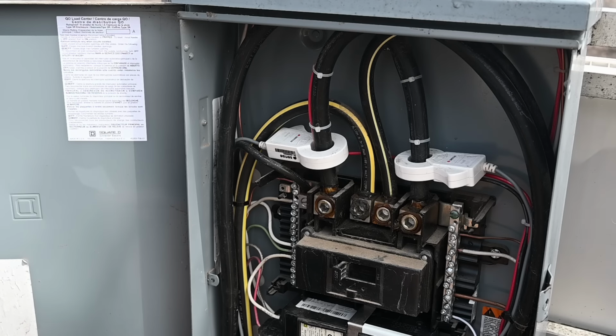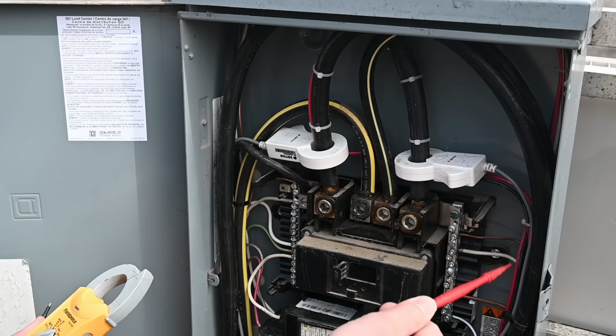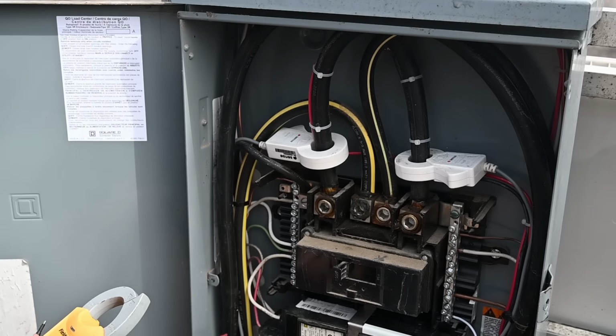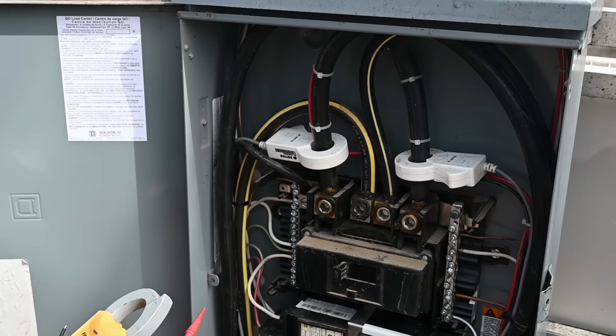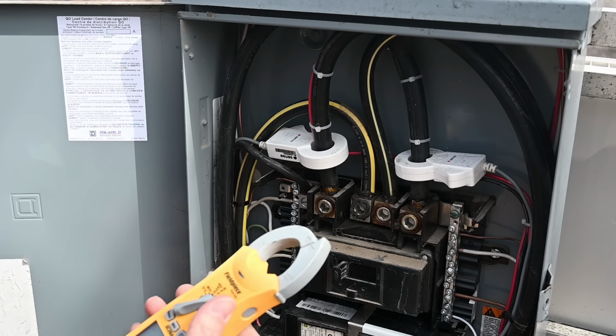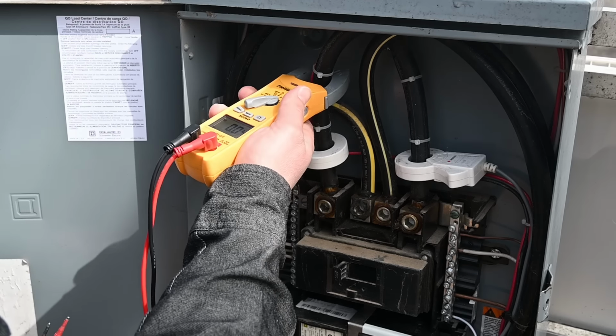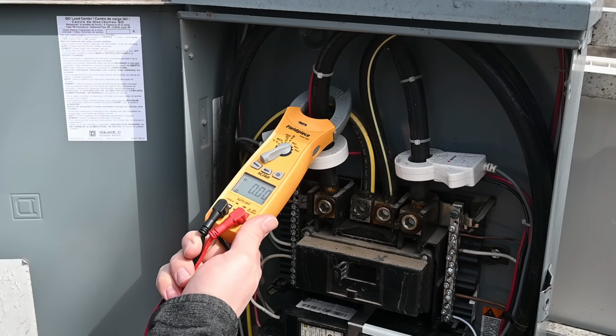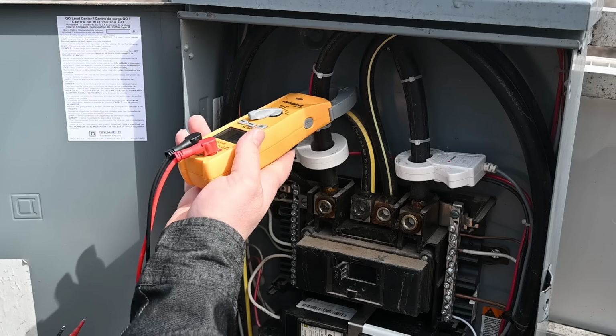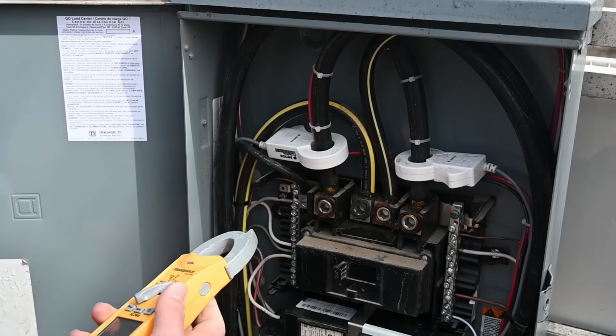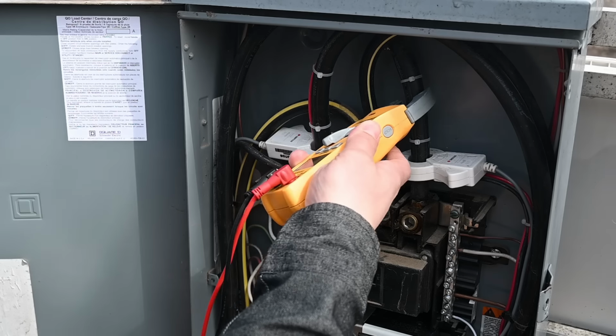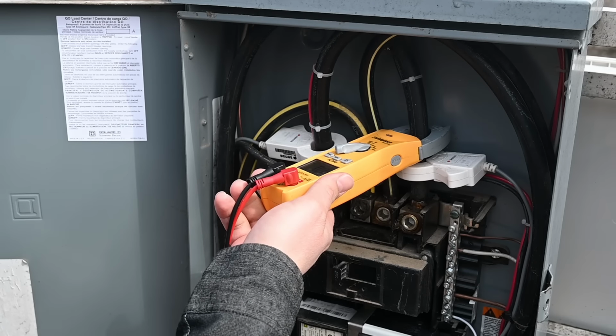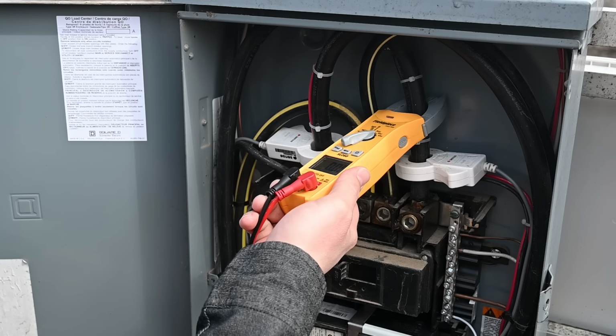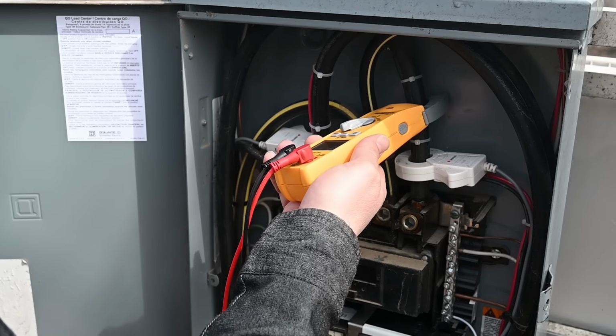Be extremely cautious when working in any live electrical panel, and I wouldn't recommend it unless you're qualified. Our power coming into this panel is this wire right here, as well as this wire right there. We'll test those to see if any current is being drawn. On this leg, we have 0.00 amps, exactly what we'd expect given that our main breaker is turned off. And right here, we're also drawing 0.00 amps, exactly what we were hoping for.